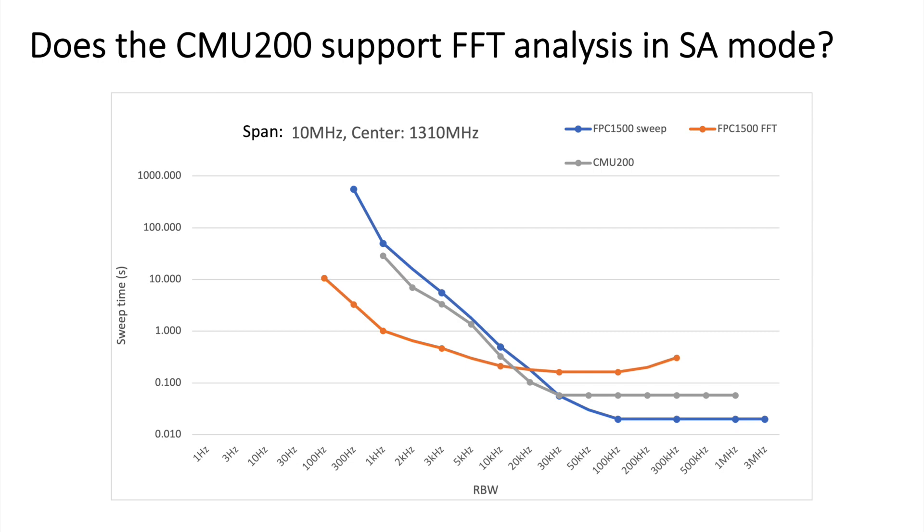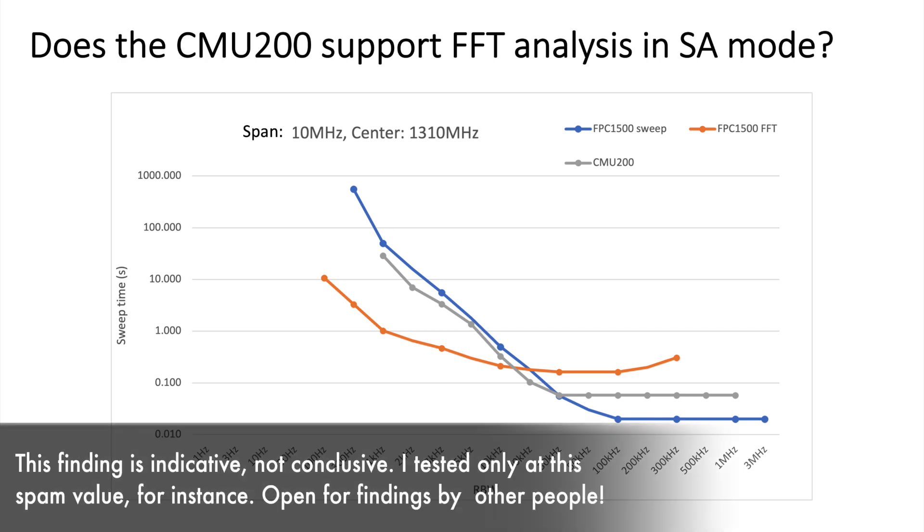So we can use the same methodology that we used today and try to get a bit of better understanding for what is the situation with this CMU 200. So what do we get here? I'm showing you the same results here as we just had for the FPC, but in gray I added the values as I measured them on the Rohde & Schwarz CMU. You will see the settings are slightly different, the choices that you have for resolution bandwidth, so I had to interpolate a little bit on the lines of the FPC. But what we basically see is that the gray line of the CMU very much looks like the sweep line on the FPC analyzer, and this seemed to suggest to me at least that the CMU really does not have FFT functionality, even though some people have expressed their expectations that it would be there. But for me this really looks much more like a classic sweep device than a device that uses FFT in its regular type of spectrum analysis functionality.